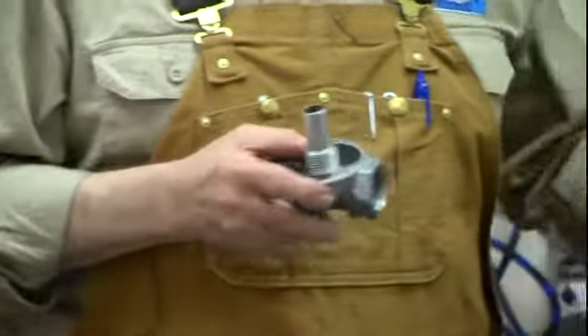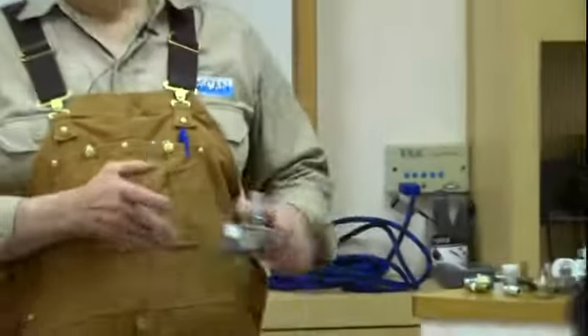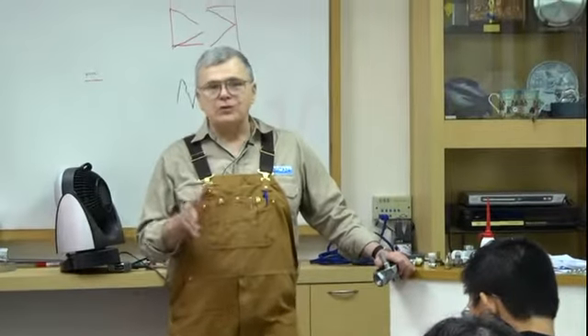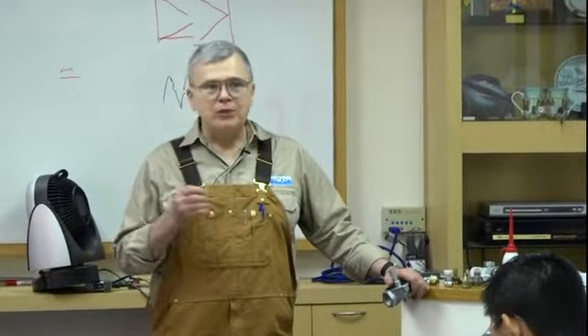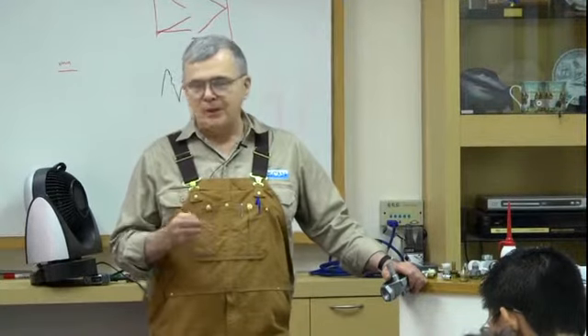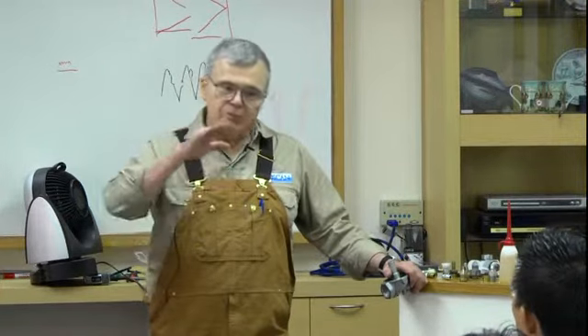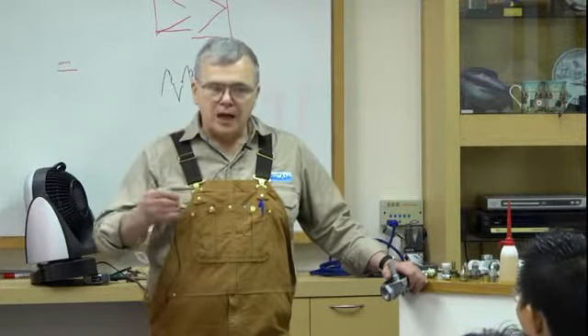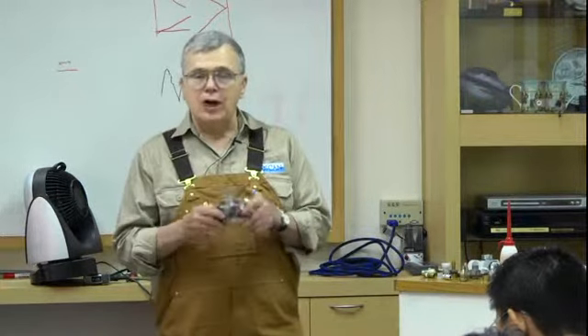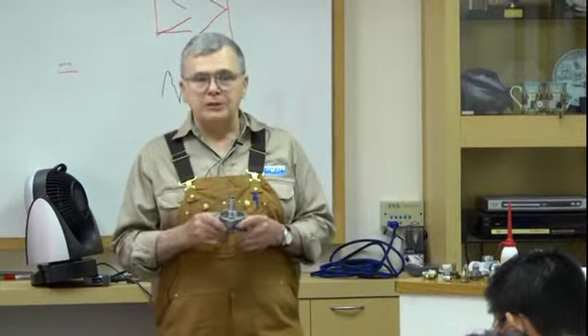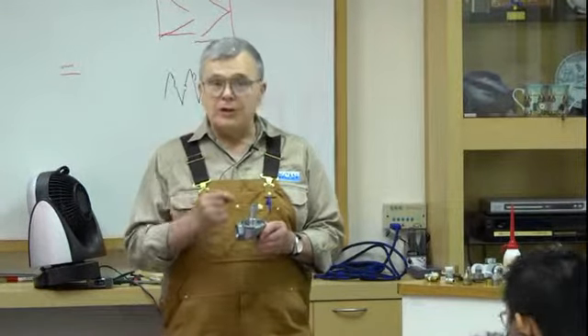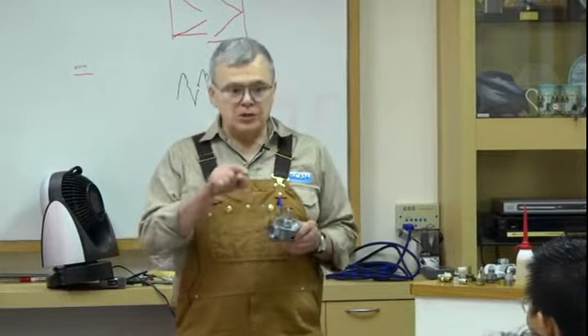Well, 2 lifetimes ago, when I took a marine diesel engineering course, old Professor Wing used to always say, nothing happens in no time. And what that means is it takes time for those check valves to close and seat. So when the pump is on the downstroke, a little bit of fuel will get by it. Having the vapor on the top of the standpipe accumulator gives a place for that very tiny amount of fuel to go to, so it does not impact the rotor and the sensor.